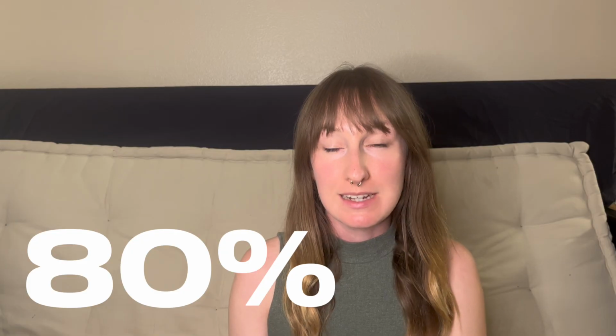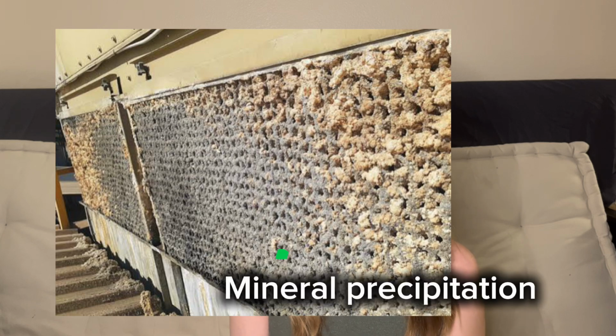According to the EESI, approximately 80% of the water withdrawn by data centers evaporates. What doesn't evaporate gets recirculated, but only so many times - minerals such as calcium, magnesium, and silica accumulate in the water, becoming more concentrated with each cycle, and these minerals can damage the cooling towers and other equipment, making them less efficient and necessitating fresh water eventually.